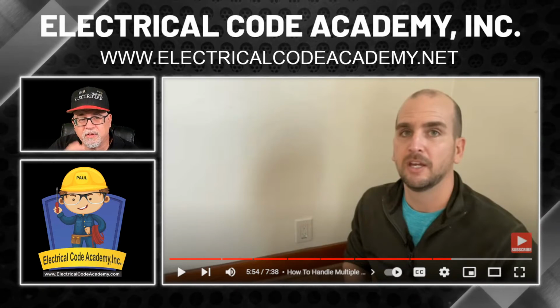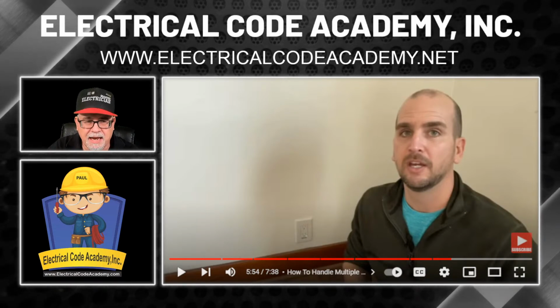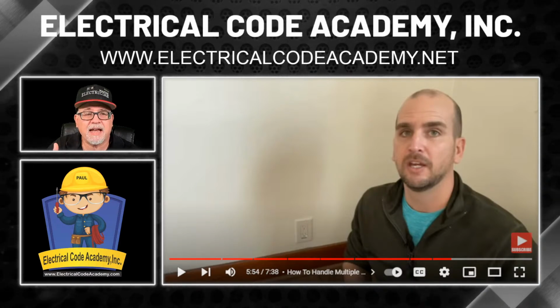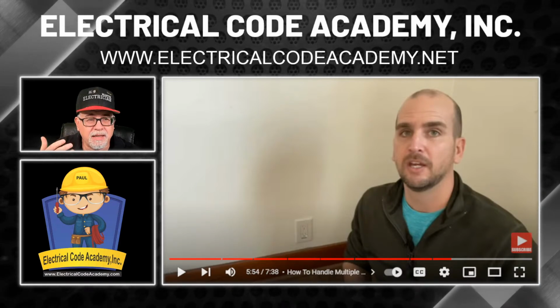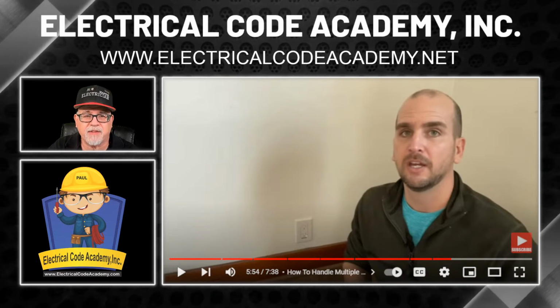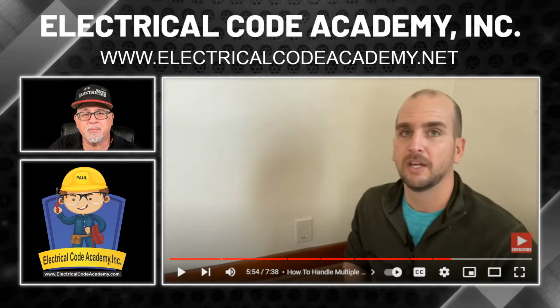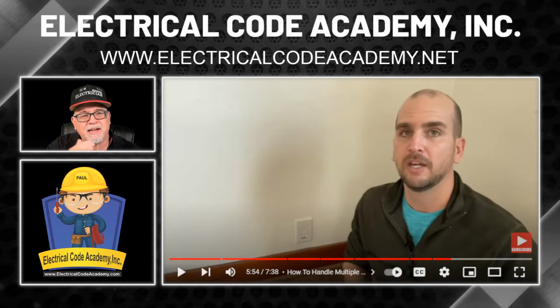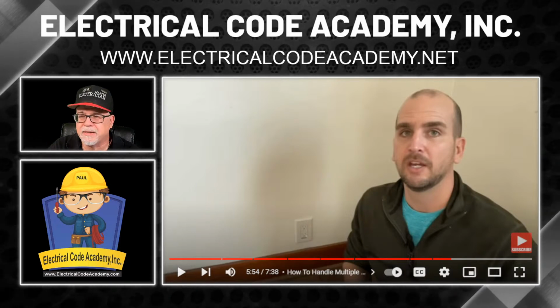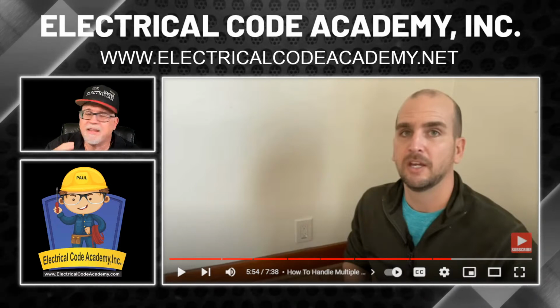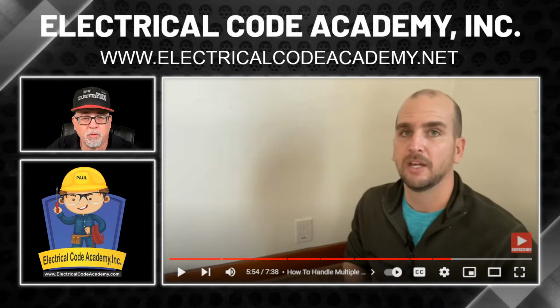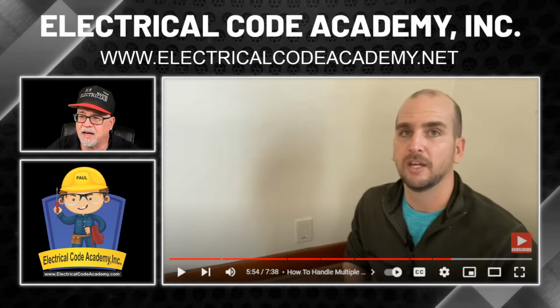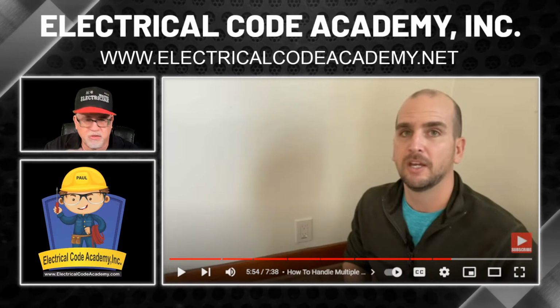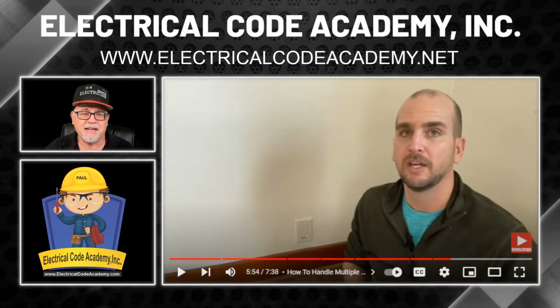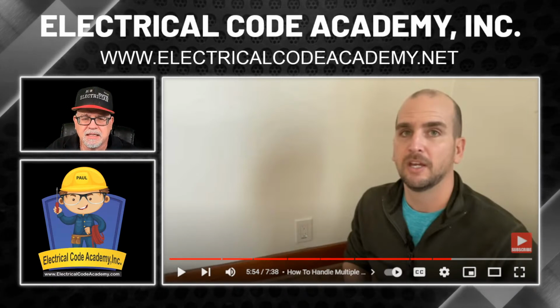And that is the 4 to 6 milliamps we call the 5 milliamp threshold. And then, of course, we have Class B, which is typically 20 milliamps or 30 milliamps, depending on the manufacturer. That is not going to protect people. That's more for protecting property and equipment that's connected to it, things like that. And then it starts getting into things we call special purpose GFCIs, and again, for three-phase applications and whatnot. So again, a bunch of different classes of GFCIs that we have.